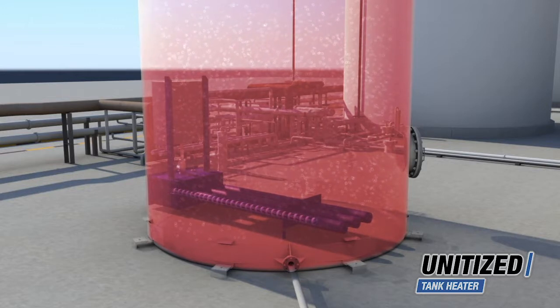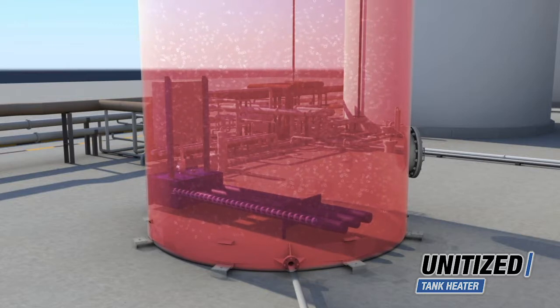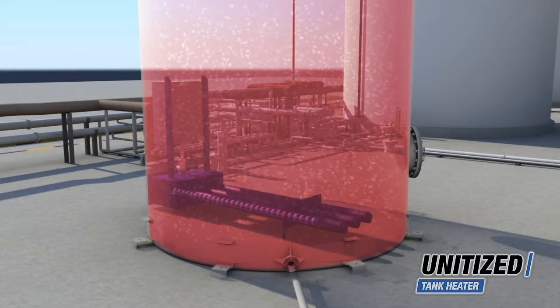These heaters feature Process Heating's drywell-style elements that reside inside the sheath, making them accessible from outside of the tank and eliminating the need to drain the tank to service the elements.